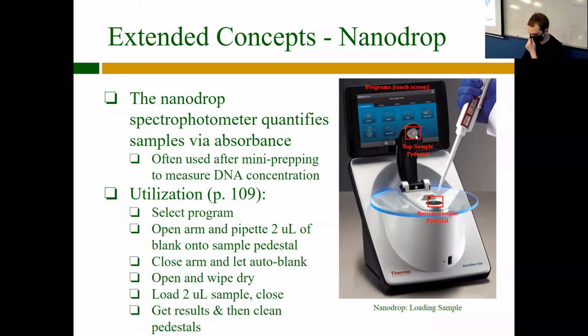And then you'll do the exact same procedure for your sample. So you have your DNA, you pull out 2 microliters, you load it onto the pedestal, close the arm, it'll read it, and then you're pretty much done at that point. Of course, at the very end, make sure to clean it. This is a Nanodrop that labs use regularly. It's in microbiome labs, so make sure it's clean for everyone else to use.